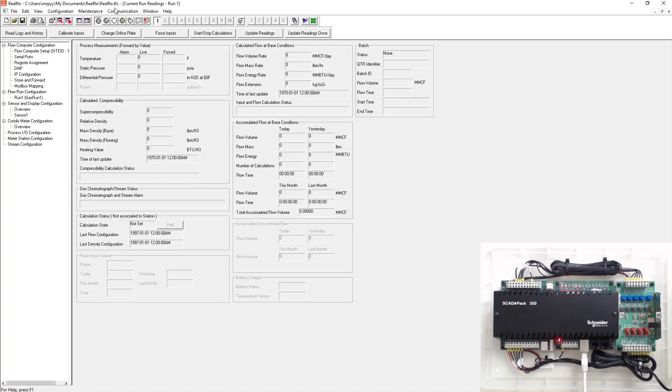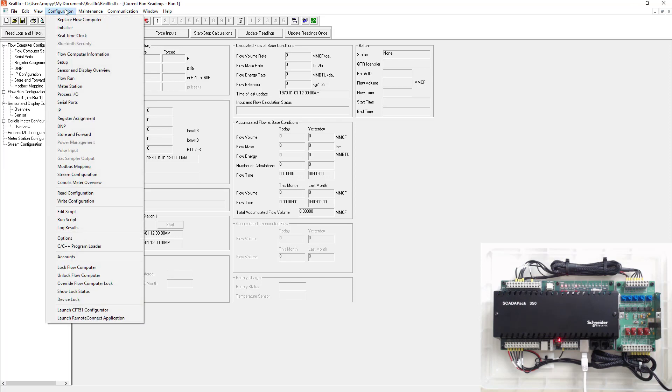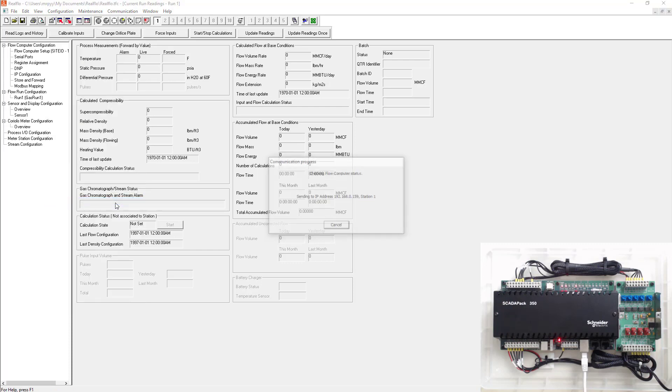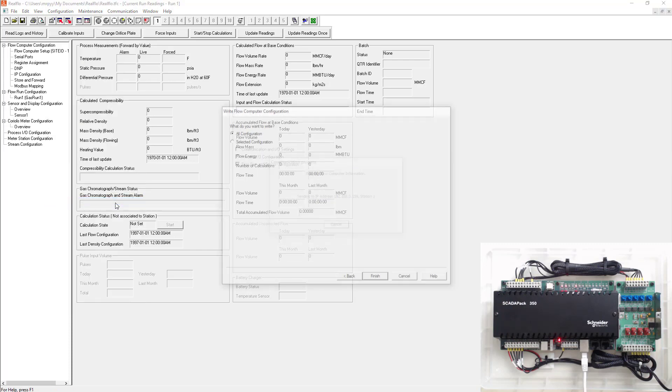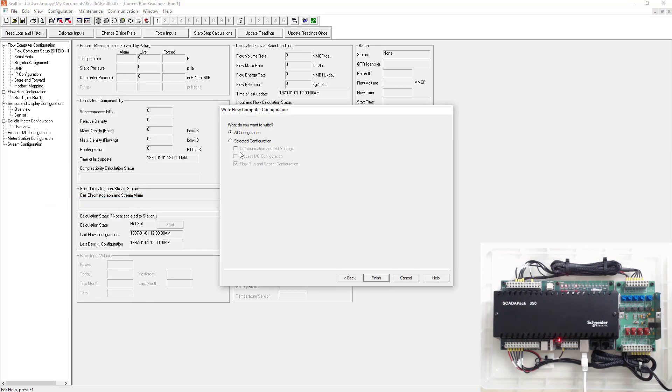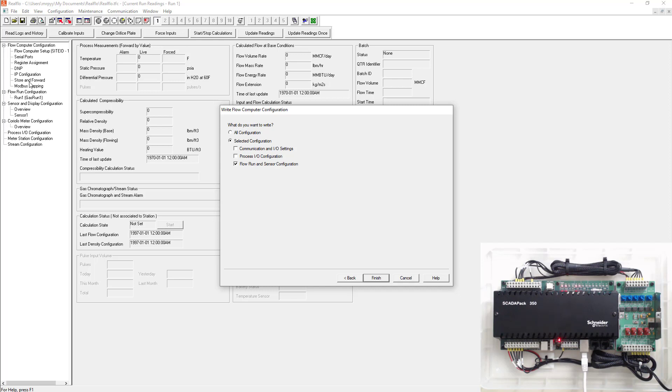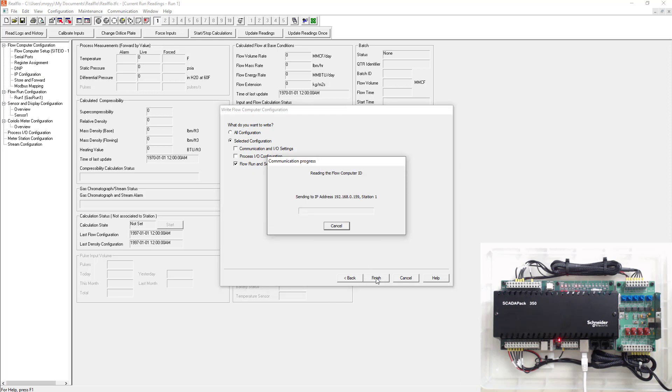So now we have our configuration here. Now we want to write this to the SCADA pack. So we'll go up to the top. We'll go configuration, write configuration. When you do that, this is extremely important. Typically always select selected configuration, flow run and sensor config. So what this is going to do, it's only going to write the run configuration and the sensor config. It's not going to change or write any of this stuff. So serial ports or IP or register assignment, anything like that, we're going to handle in TelePACE. Everything else we're going to handle in RealFlo. So in RealFlo, we're just going to handle the flow run and sensor config. So correct. Finish.